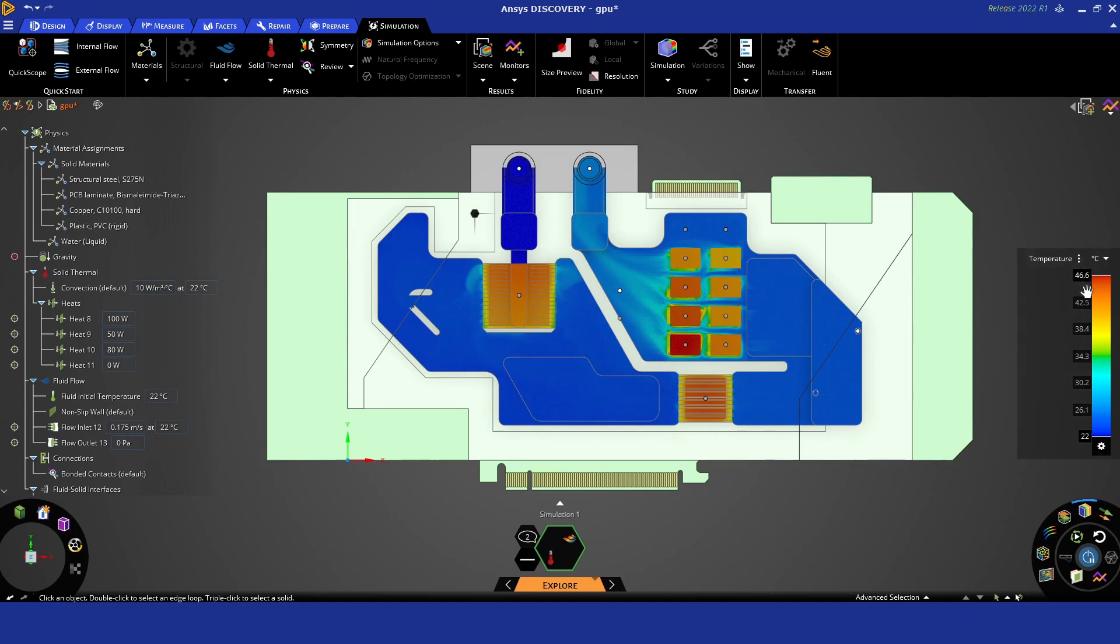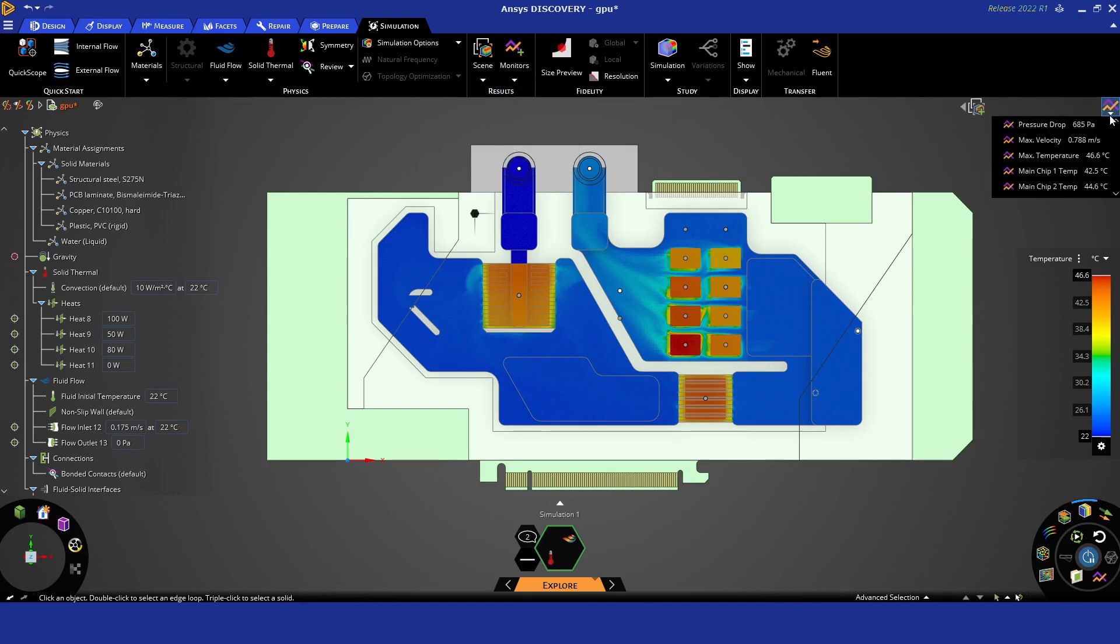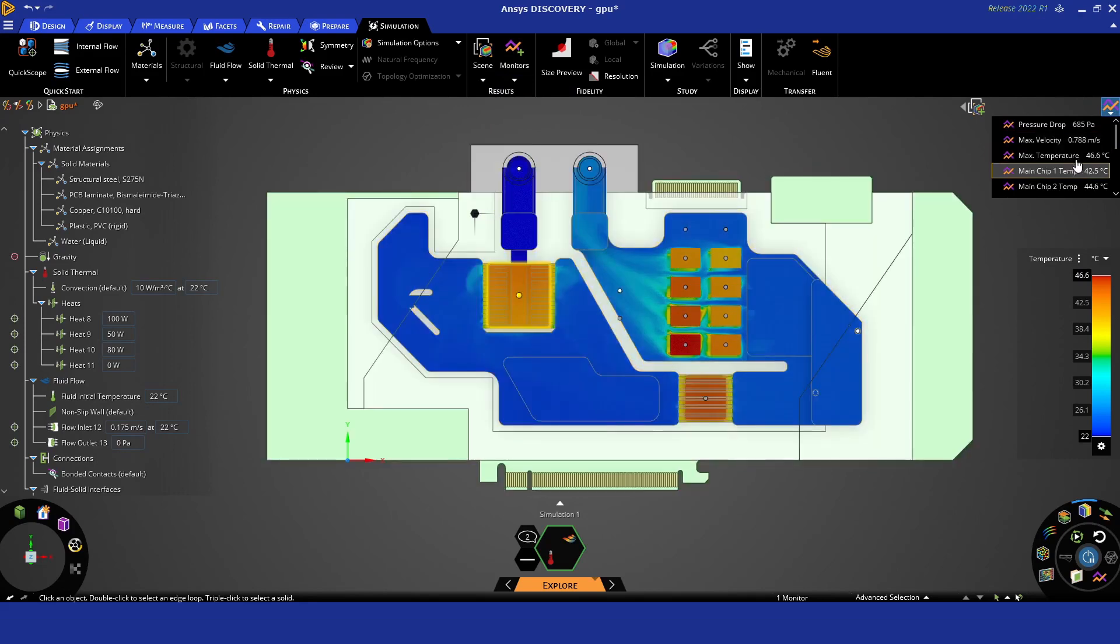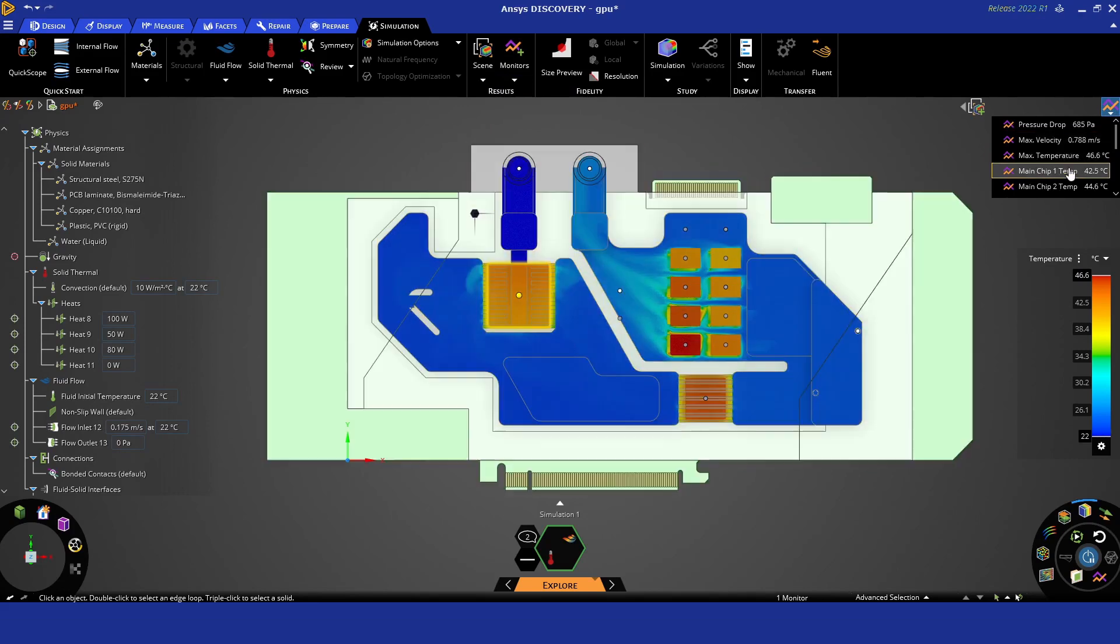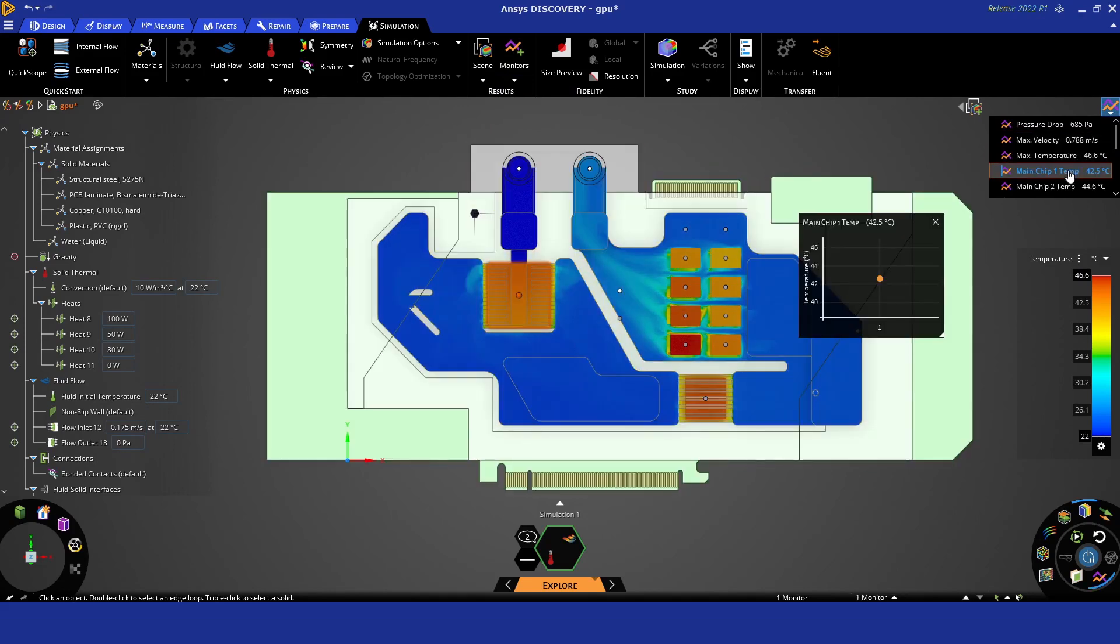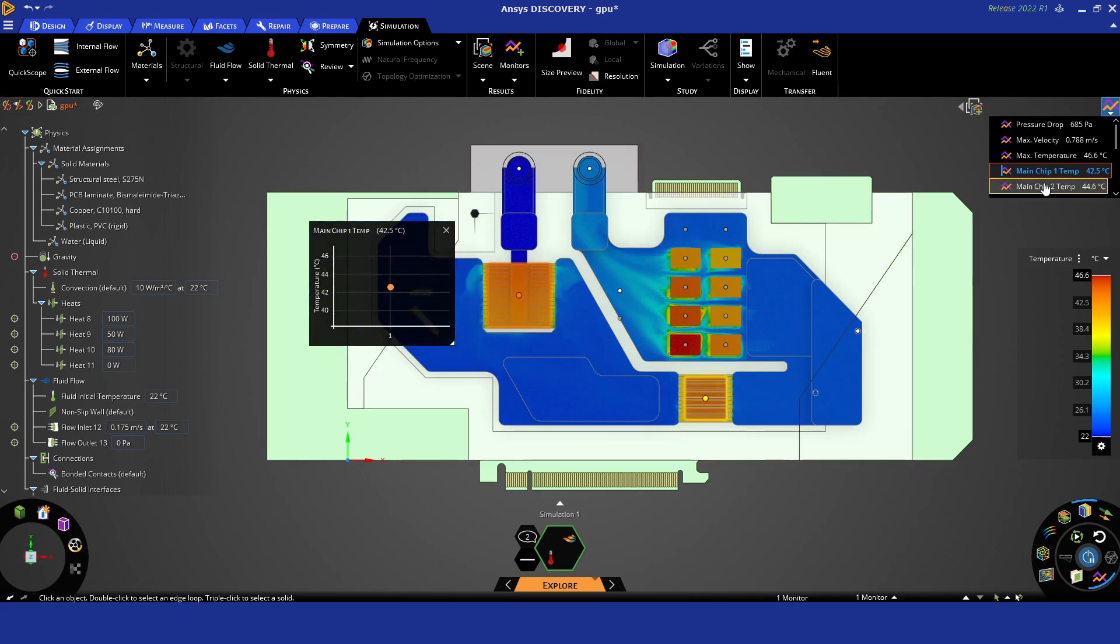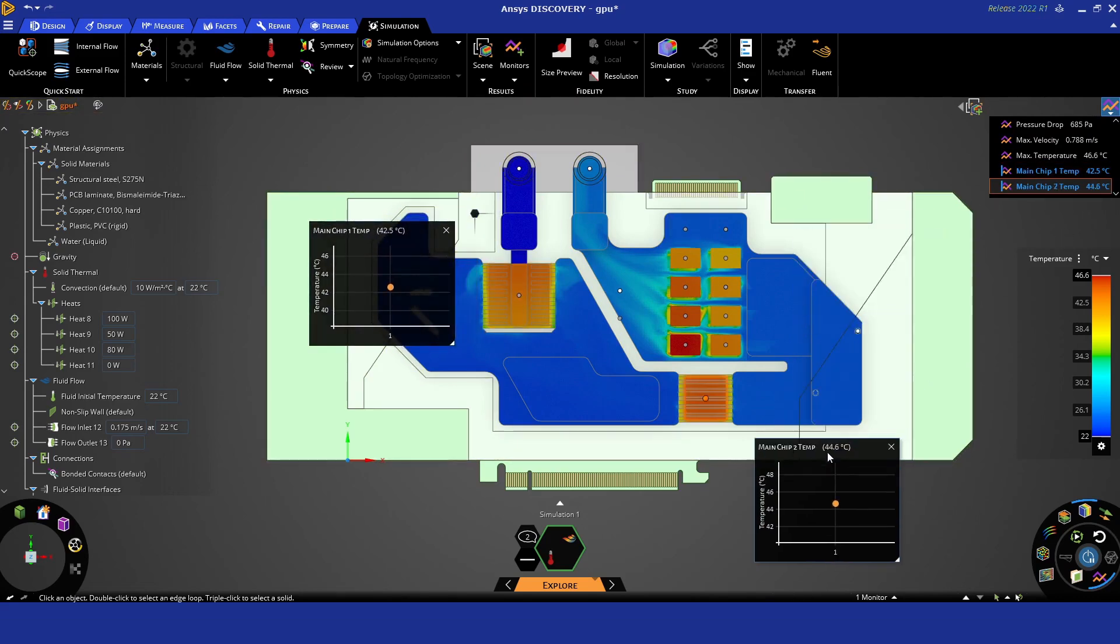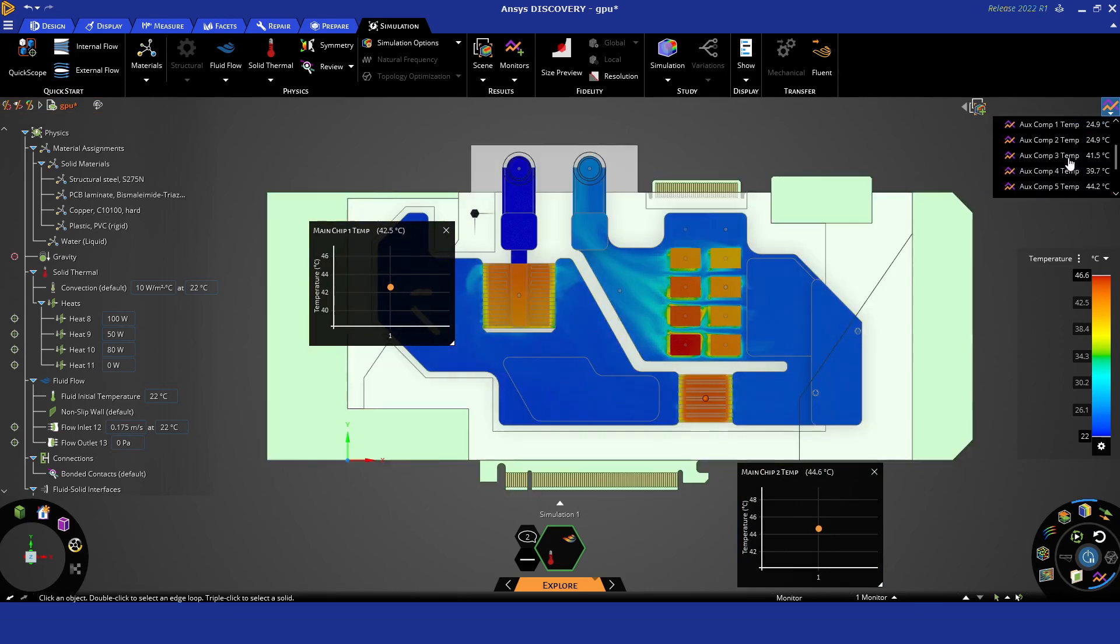With the first solution complete, we'll have a quick look at the results. You can see the peak temperature is about 46.6 degrees. That's generated from the monitors menu. In this case we've actually queried every single chip on the board. We'll just show a couple here for example purposes—main chip one and two are shown.